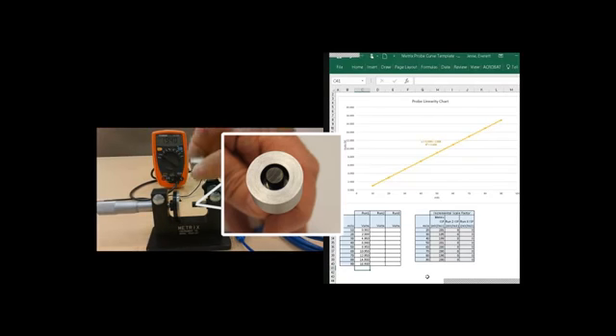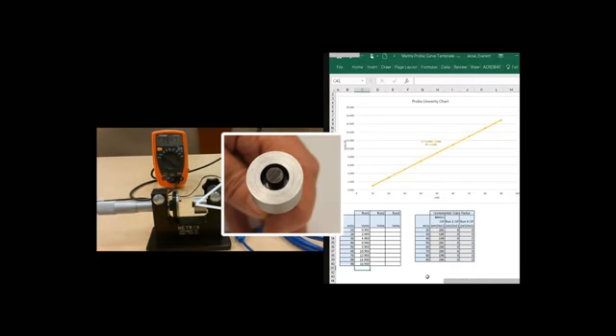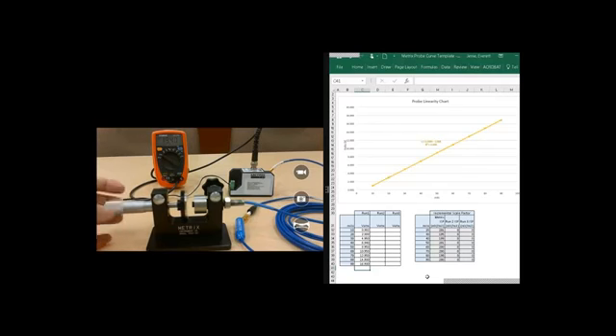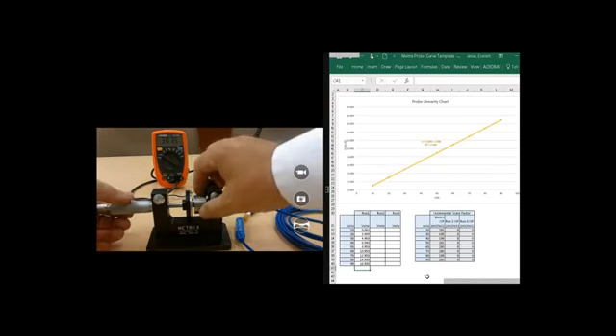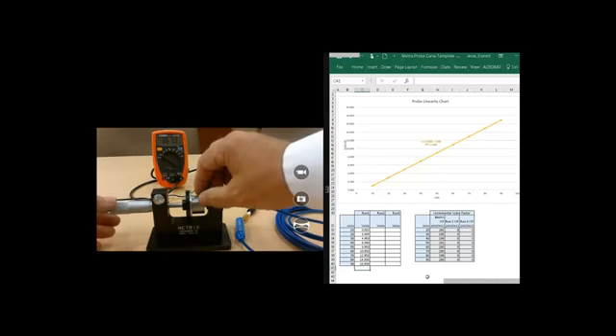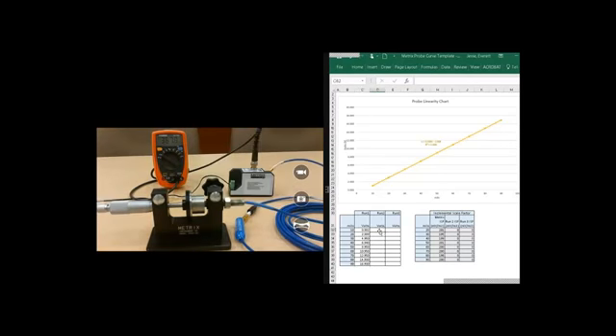Without making any changes to the DPS, we'll mount the fixture on the static calibrator and run another probe calibration check. Notice that we place the probe tip and fixture parallel with each other by first having the 4140 steel target meet up with the probe, and then we gently rotate the fixture so it is in contact with the 4140 steel target. For the first 10 or 20 mils, we will hold the fixture so it does not rotate. We'll record DC voltages in 10 mil increments as before.